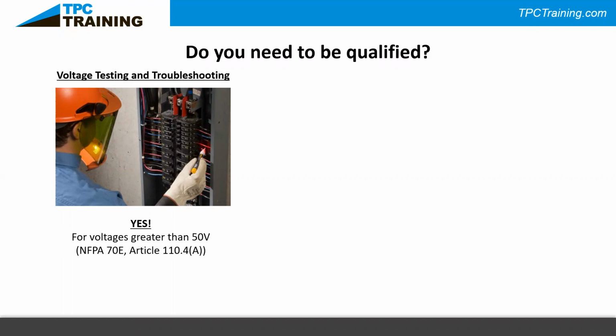I'll take it one step further, and this will help with the next task, which is what someone was mentioning: anytime you are faced with exposed energized conductors and you're getting closer than the limited approach boundary to those conductors. I know you might be crossing your eyes if you haven't taken an arc flash safety class in a while on what the limited approach boundary is, but it's within a couple feet or so — could be 3.5 feet, 42 inches for most industrial voltages like 120 and 480 volts. If you're getting closer than 3.5 feet to equipment that's open and exposed to you, then you must be qualified to work on it. Whether you're working near it, on it, or testing it, you need to be qualified.